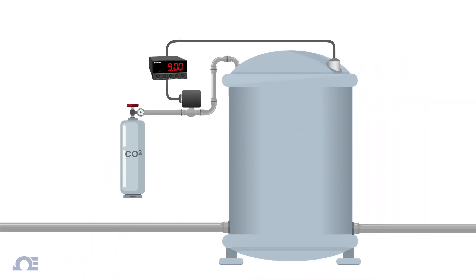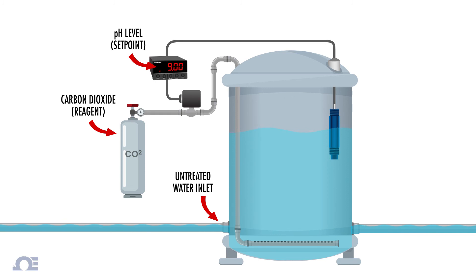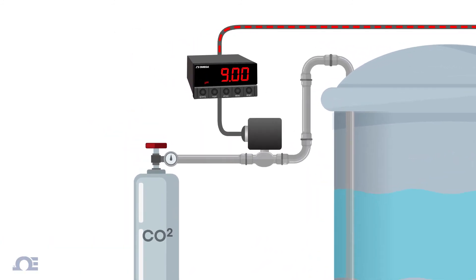In this example of a water treatment system, a pH level of 9 is maintained using carbon dioxide as a reagent. Untreated water flowing into the tank is monitored by the pH electrode. The electrode sends its signal to the controller, where the set point is compared to the incoming electrode signal.